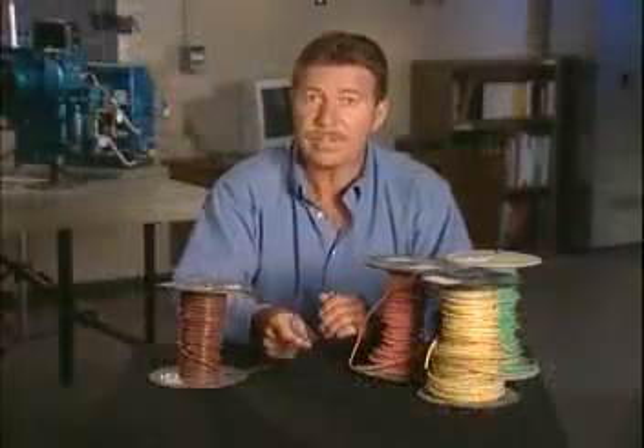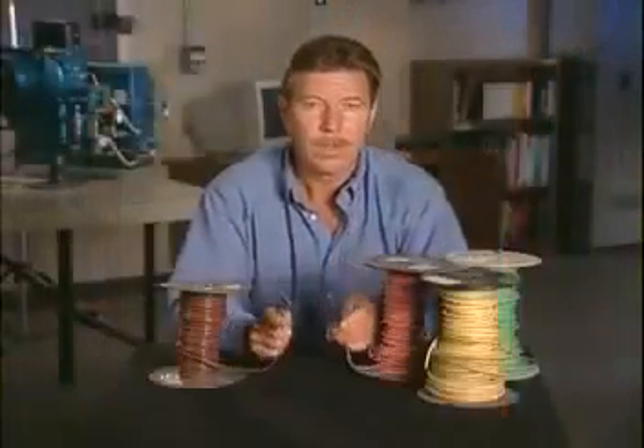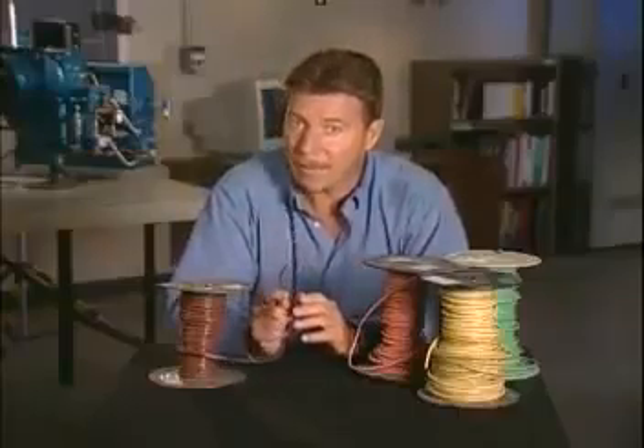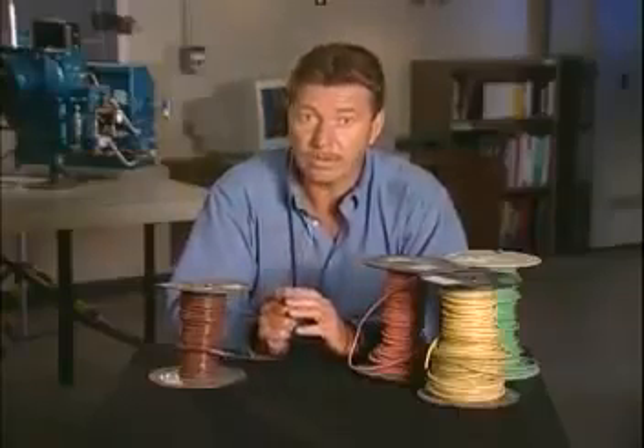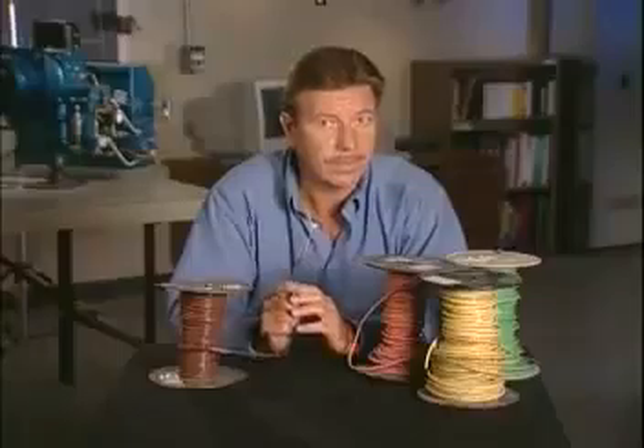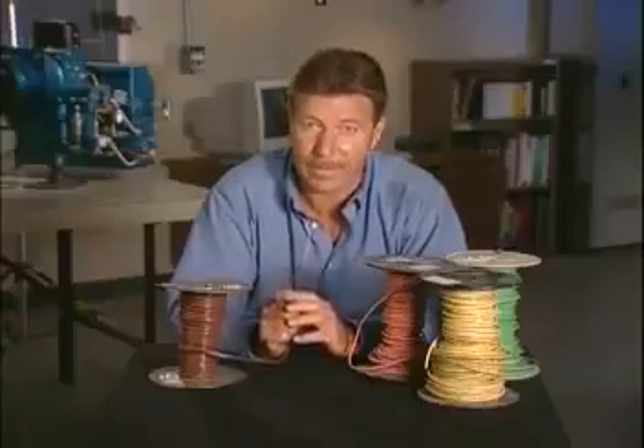Industrial and commercial control circuit wiring is similar to that used in a residential system, even though the power circuit wiring may be three-phase, or at least 240-volt single-phase. The size of the conductors used in control circuits is typically smaller than the conductors used in power circuits. Always be sure to follow the manufacturer's guidelines when installing control circuits to be sure that the conductors are properly sized for the application.